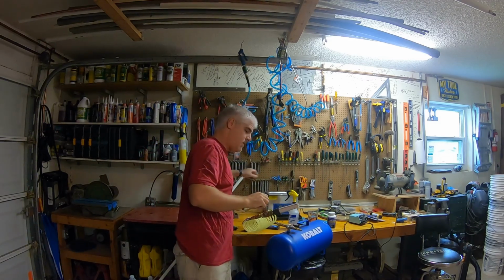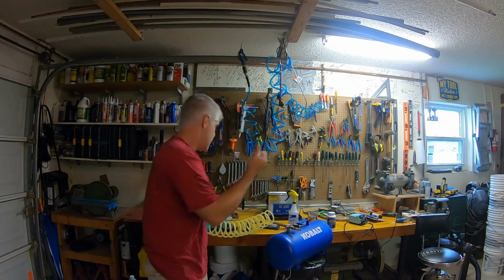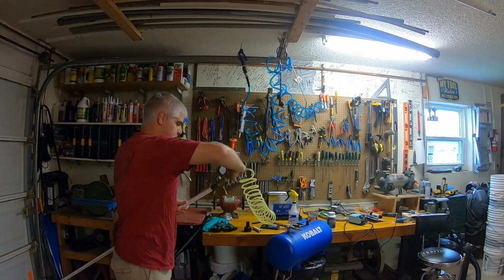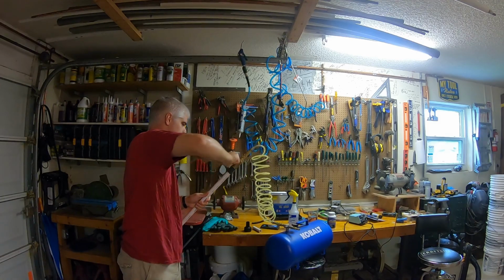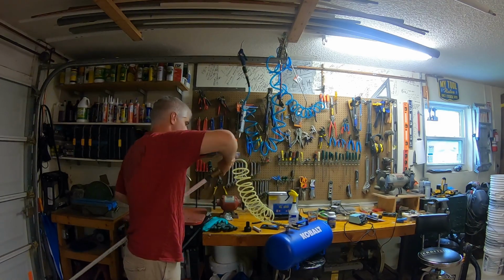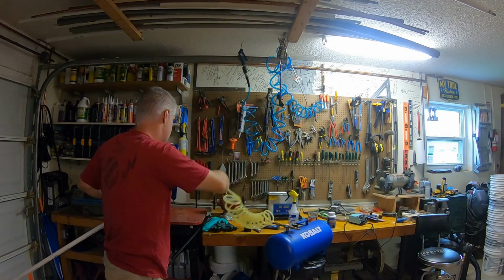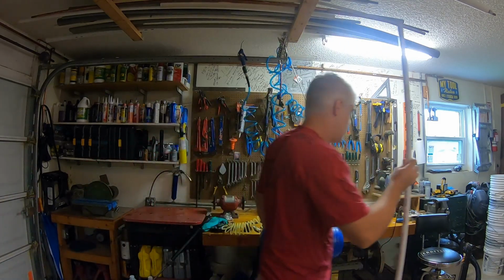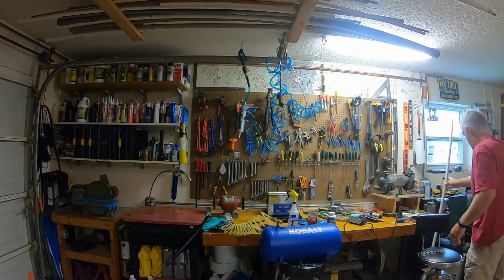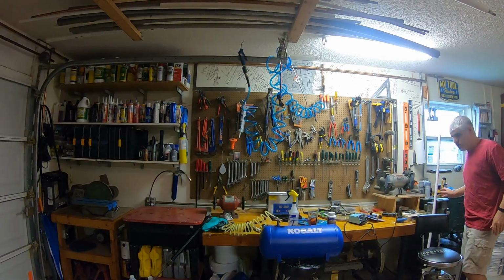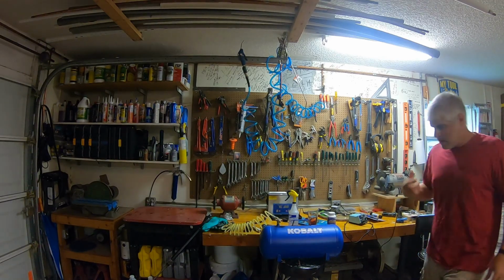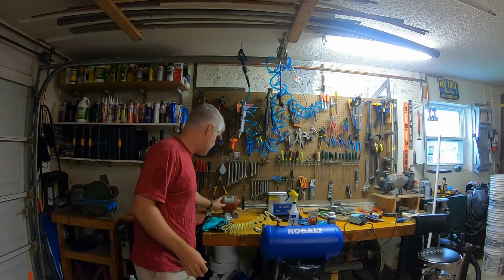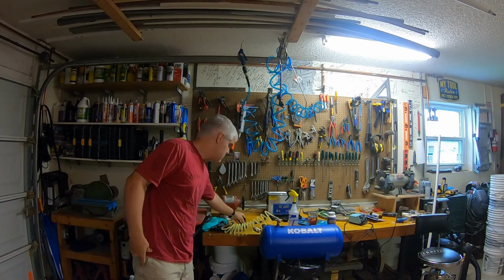So like I said, you cut the PVC off. In my case, I'd be dealing with the male pipe in my attic because I just cut off a piece. You hook that up, like so, and just pulse it with air. So that's along the lines of what an AC guy would do. In fact, that's what they typically do. Some will try to suck the lines out with this type of a tool, and others will try to blow it out. Both will work.